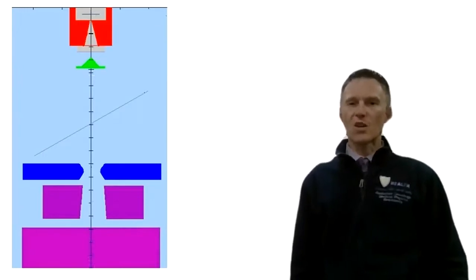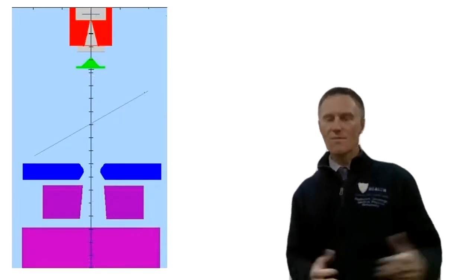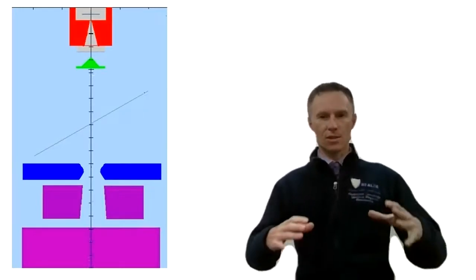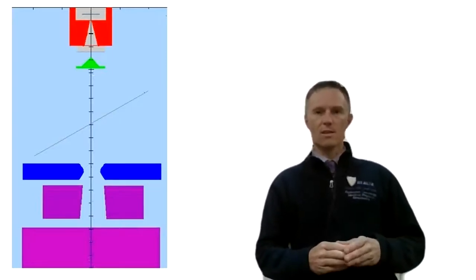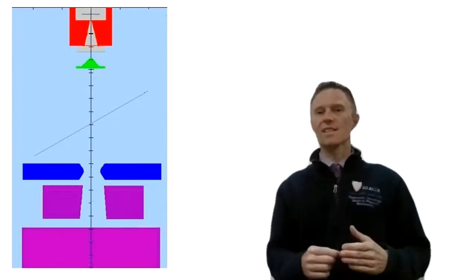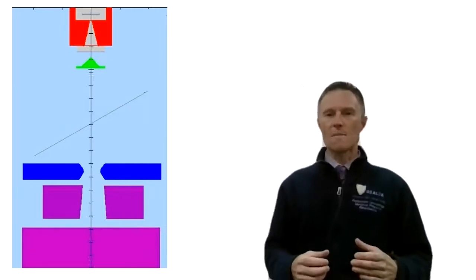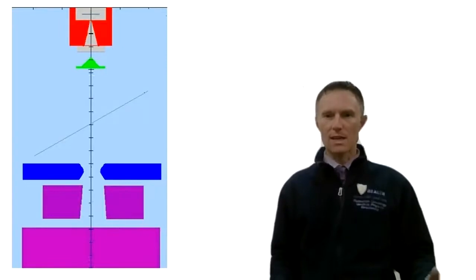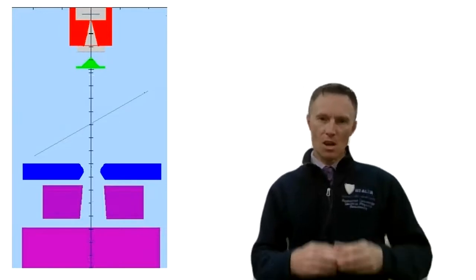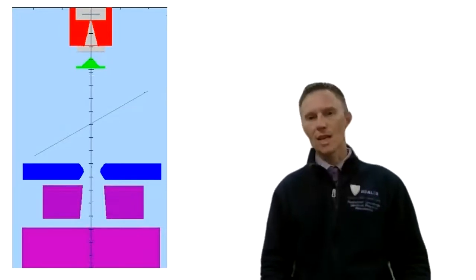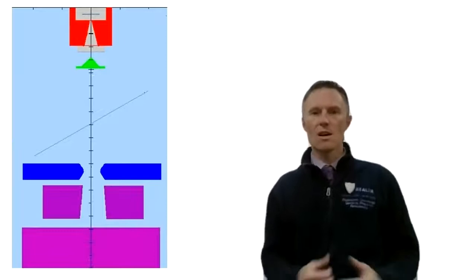Starting at the very top of this image, what we're looking at here in red is called the primary collimator. The primary collimator is essentially just a conical hole that produces a beam of circular cross section. As electrons strike the target and produce a beam of photons, the cross section will be circular. The beam diverges downwards, and in order to collimate that so it doesn't spill out over the sides of the jaws, the primary collimator is used.